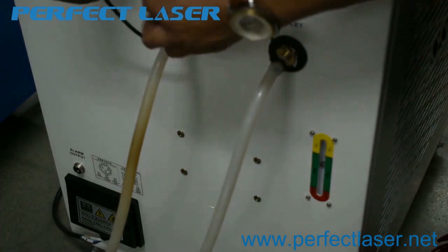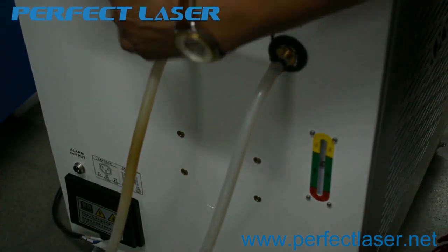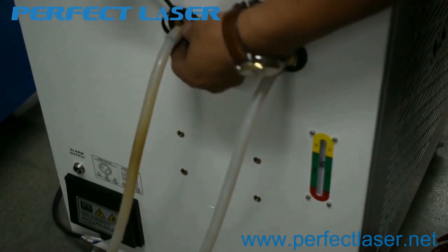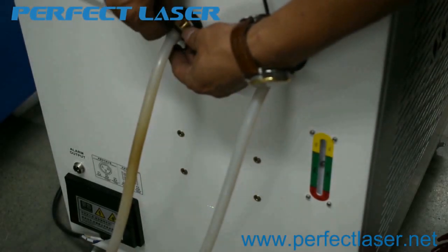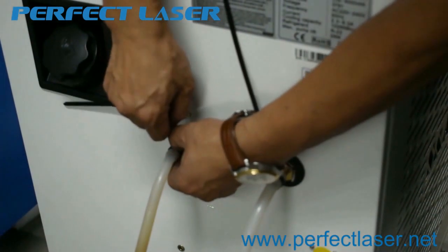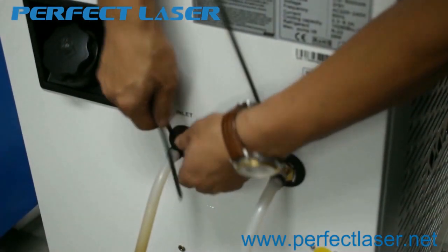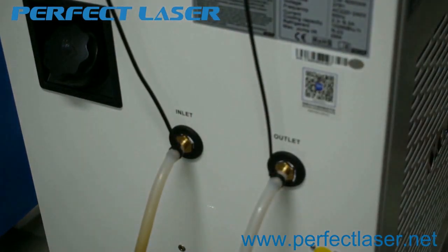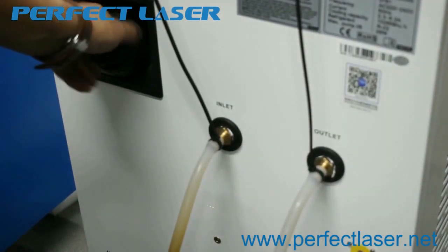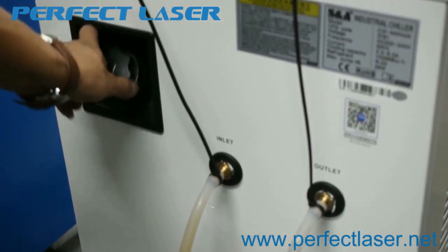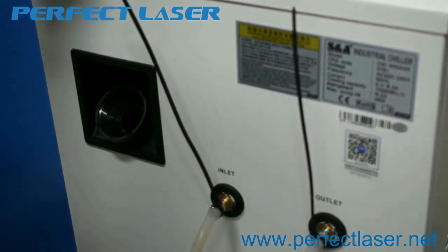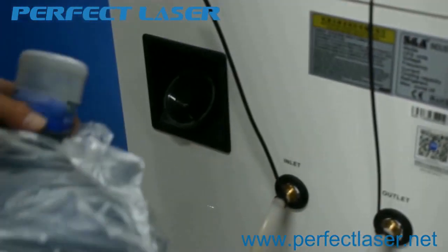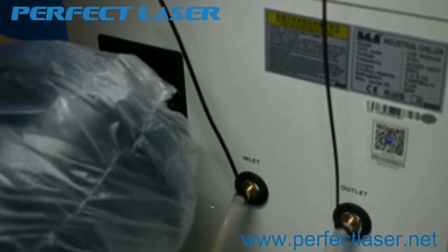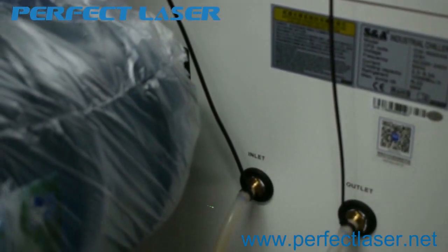And tighten this part. Make sure there's no water leaked out. After finishing connecting the water pipe, we open the tank of the water chiller and use distilled water or pure water to put the water into the water chiller.